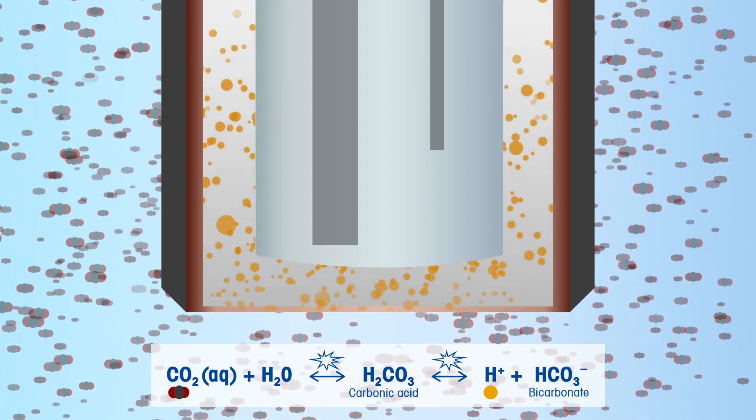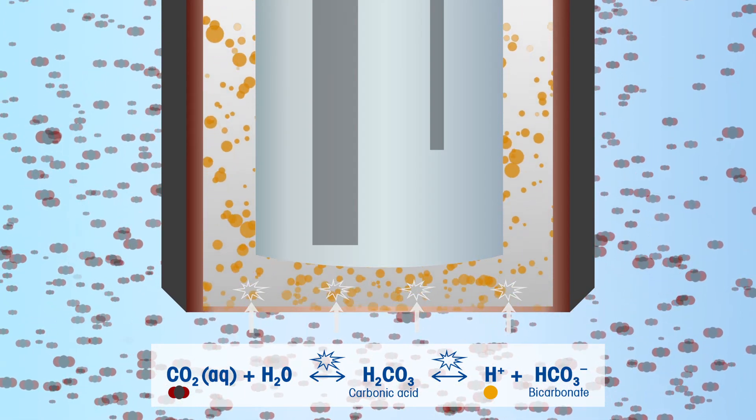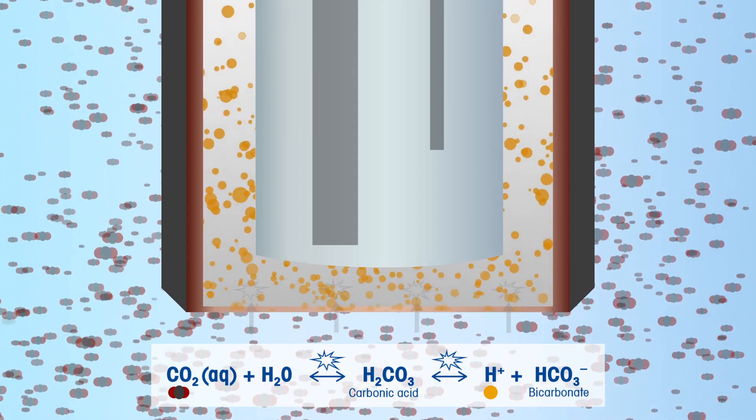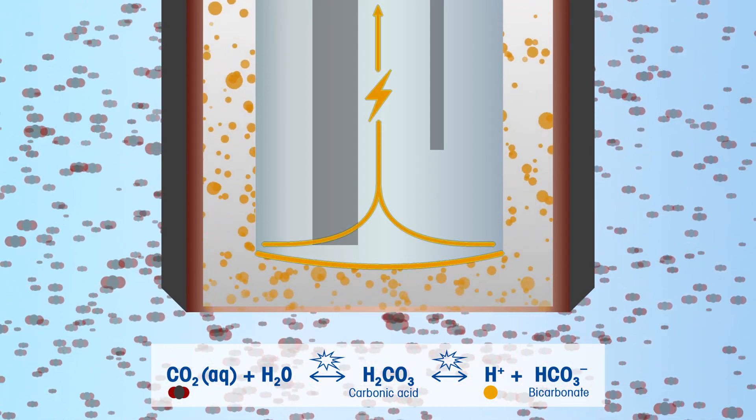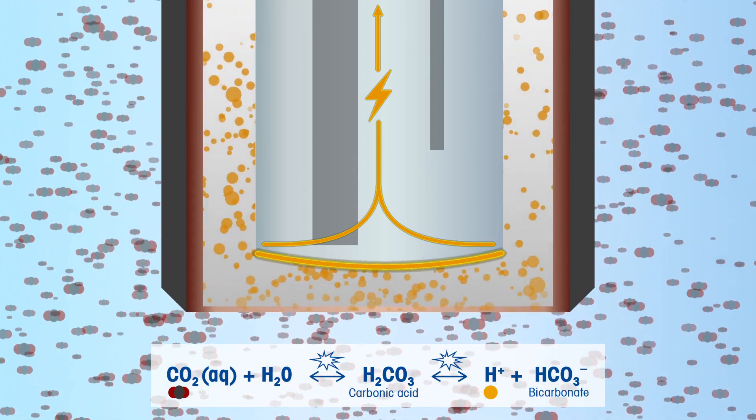The InPro 5000i measures dissolved CO2 following the Severinghaus principle, where CO2 gas permeates through a membrane and reacts with a bicarbonate electrolyte solution. A pH electrode immersed in the electrolyte measures the pH change. This change is dependent on the dissolved CO2 concentration in the liquid being measured.